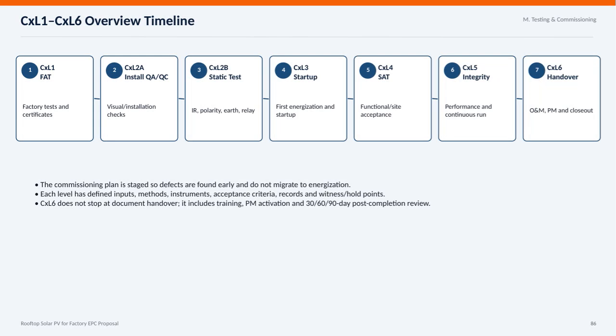Here we have an overview timeline for the testing and commissioning phases, covering levels CXL1 through CXL6 for the rooftop solar PV project. Starting with CXL1, we focus on factory acceptance tests, which include factory tests and certification to ensure quality from the source. Next, at CXL2A, we perform installation quality assurance and quality control through visual and installation checks. Then in CXL2B, we conduct static tests like insulation resistance, polarity, earth continuity, and relay functionality. Moving on to CXL3, this is the startup phase that involves the first energization and system startup.